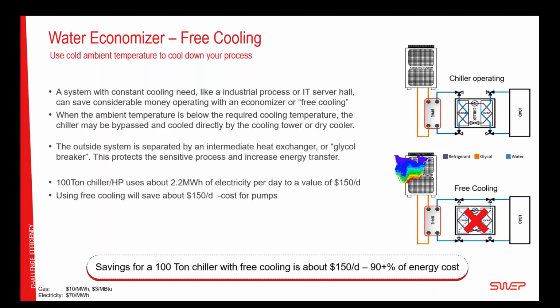And the economy of having free cooling is unquestionable, and the need for an efficient and compact heat exchanger to be able to be inactive during parts of the year, so it cannot be too big. It's taking up space, and you want to have a heat exchanger with low footprint and high efficiency to transfer the coolness from the outside to the load side while protecting the system.